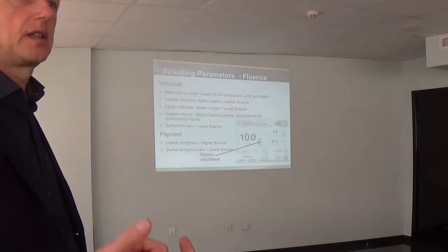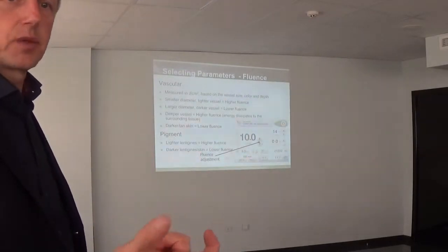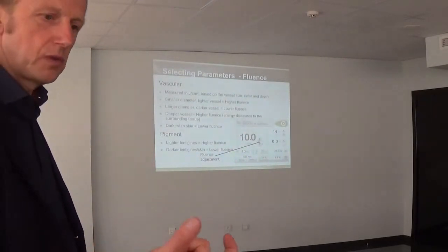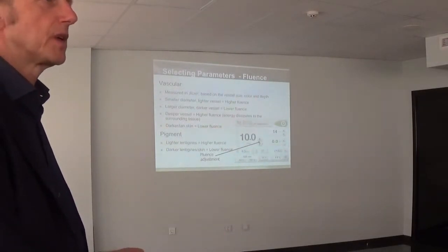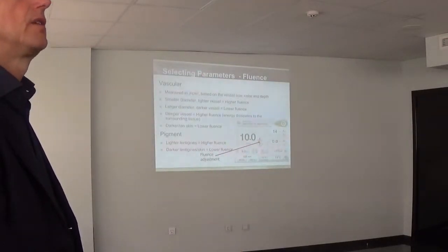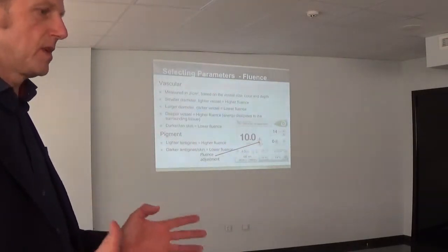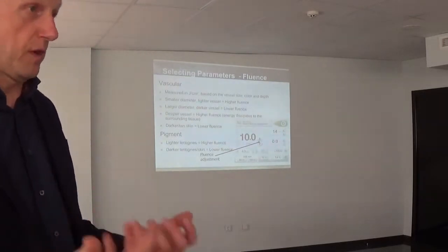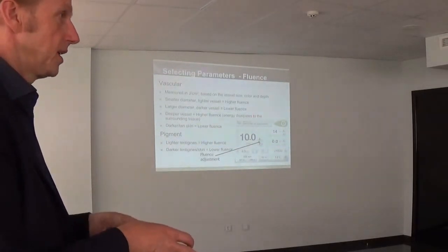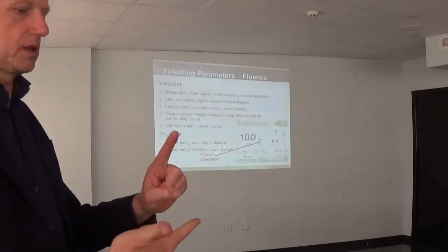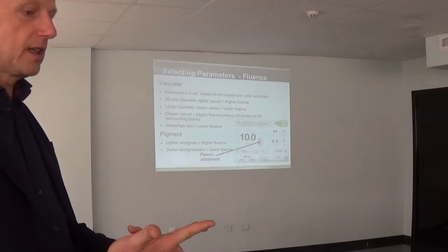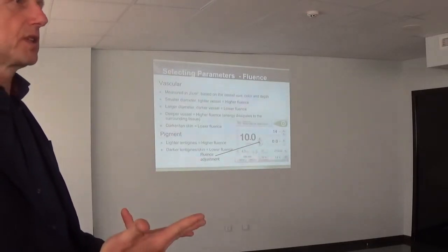In the XLV, this lens is motorized, so a motor moves the lens and makes your desired spot size. So in the XLV, you can have all combinations of parameters that are very efficient to treat one indication, all combined. It will determine the fluence, the spot size, the cooling, and the pulse duration.